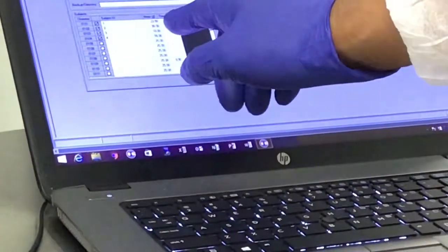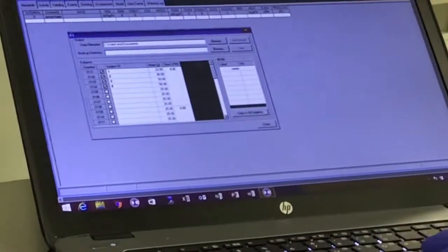So what you can do is have 8 giant mice from channel 1 to channel 8, and you set that at 1 liter, and you have 8 small mice from channel 9 to channel 16, and you set that at 0.5 liter. But 1 to 8 use the same pump, and 9 to 16 use the same pump.